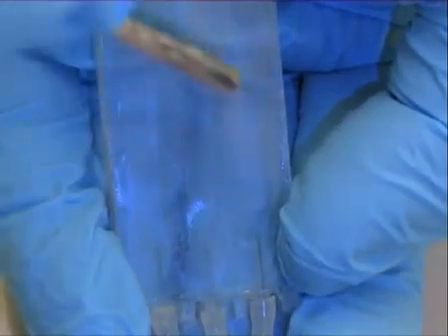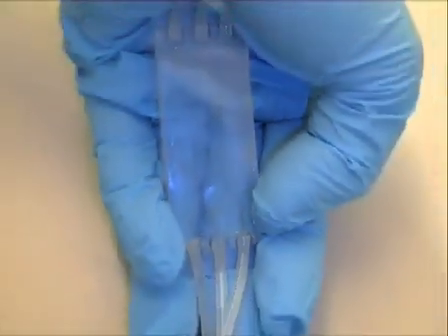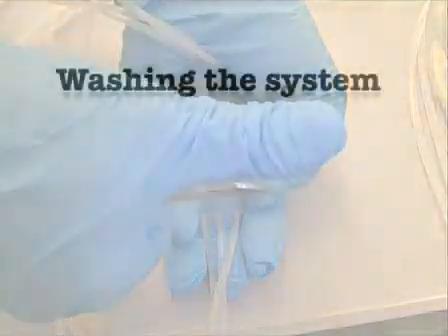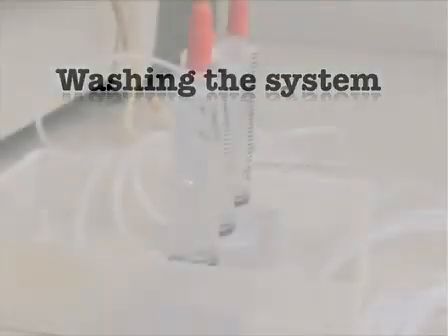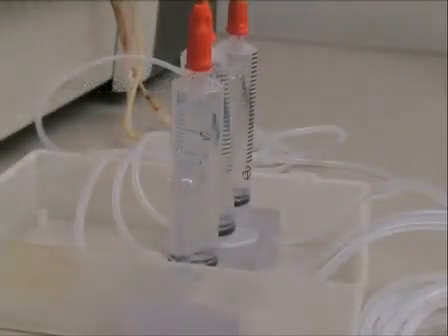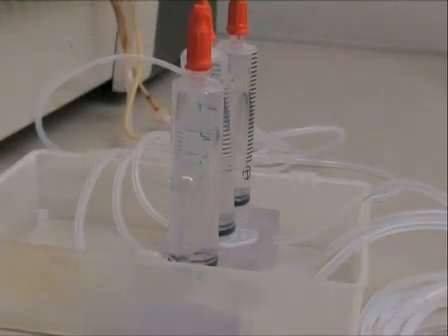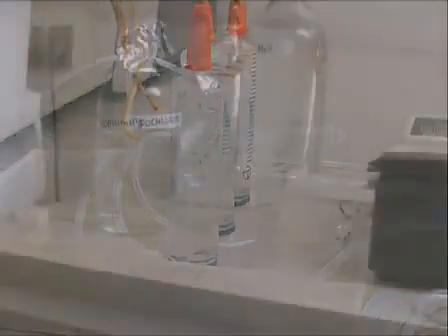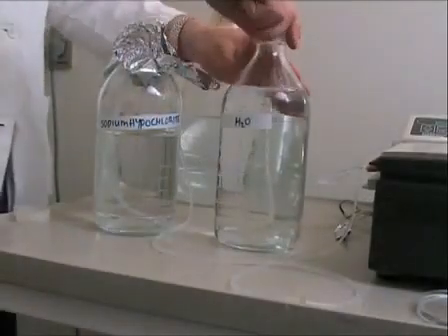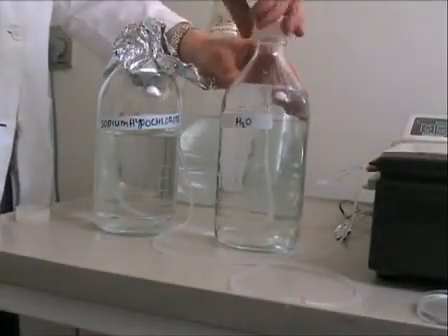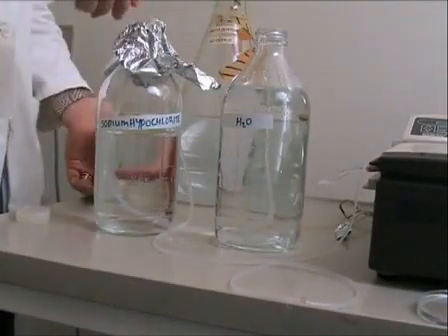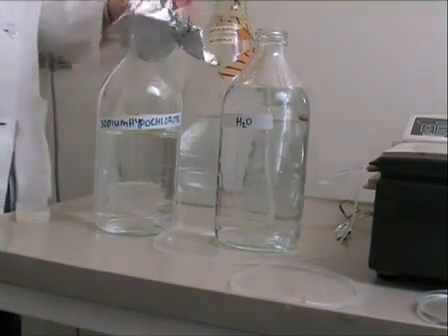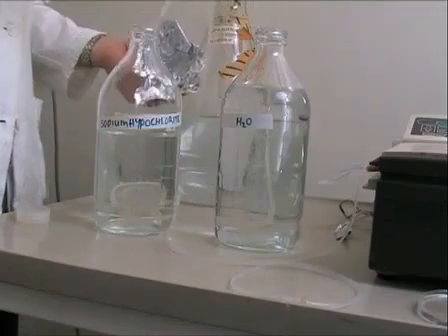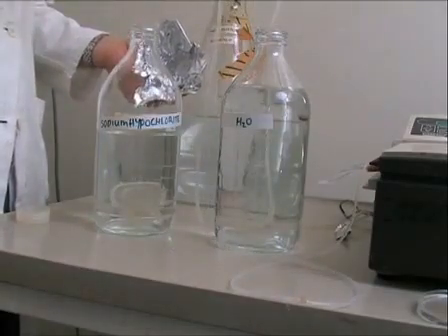Now leave the flow cells to sterilize for 3 to 4 hours at a flow of approximately 0.2 millimeters per second. Washing the system. First, empty the system by allowing air to push the hypochlorite out of the entire system. As the system now has been emptied of the hypochlorite, place the central feeding tube into a sterile bottle of water and cover the top.